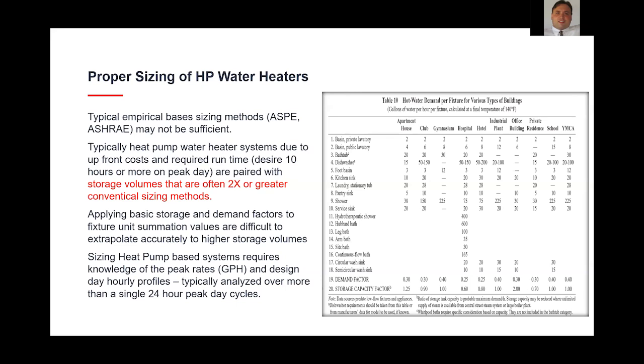And so when you start looking at typical empirical based methods by ASPE or ASHRAE, where you're adding up fixture values, gallons of water per hour per fixture, and then applying things like a demand and a storage factor to these, this is just one example of those methods out of ASHRAE. Those are difficult to extrapolate to these alternate designs. Again, you need to apply this mindset where you're going to have higher storage volumes and smaller generation outputs, recovery rates, I should say, from these heat pump water heaters, and you're trying to maximize hours of runtime.